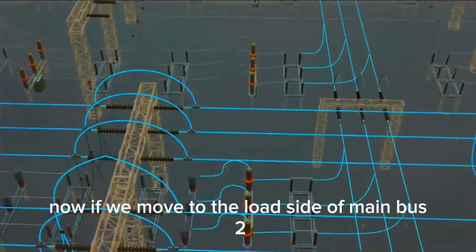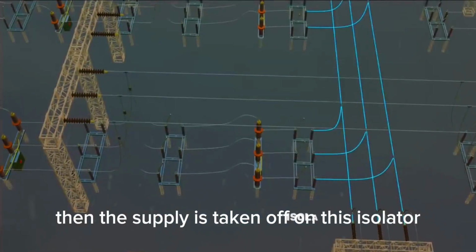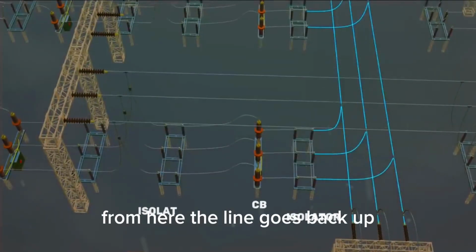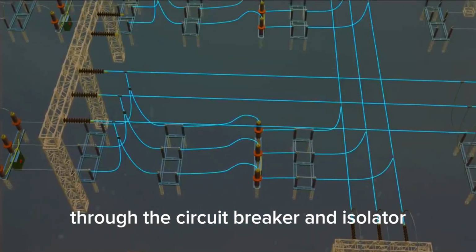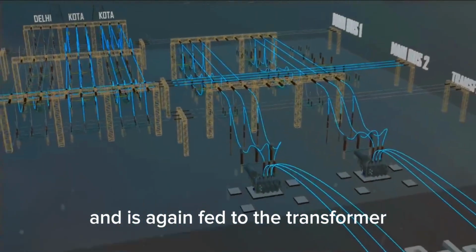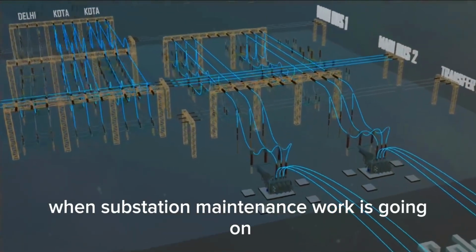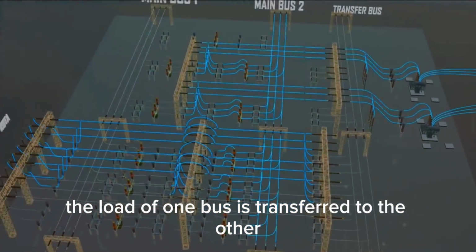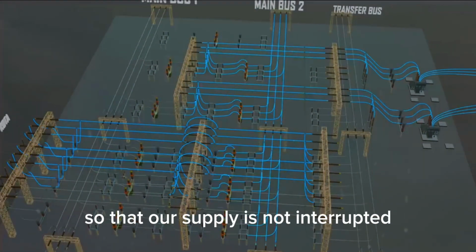Now if we move to the load side of main bus 2, then the supply is taken off on this isolator. From here, the line goes back up through the circuit breaker and isolator and is again fed to the transformer. So many times when substation maintenance work is going on, the load of one bus is transferred to the other so that our supply is not interrupted.